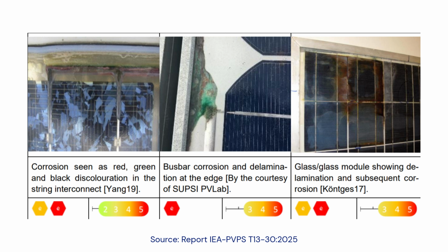Environmental factors can accelerate the corrosion, like ammonia, salt, humidity, temperature. For these reasons, corrosion is more frequent and severe under hot and humid climates or in agriculture or maritime environments. Discoloration can be also related to non-corrosive processes like a discoloration due to light-sensitive solder flux residues on the ribbon.